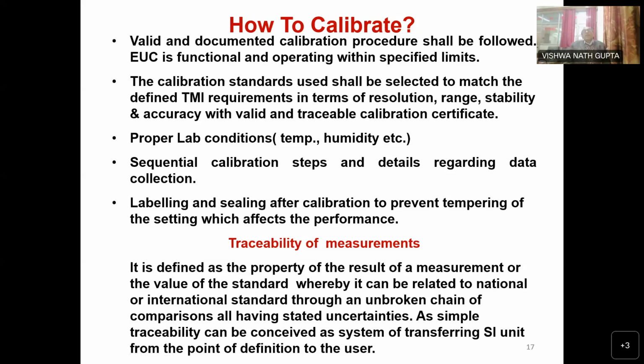Now, once we emphasize the calibration of electrical equipment for industry, the same applies to us also. Our measurements should also be traceable to national standards, meaning the chain of traceability has to be maintained. Suppose from the SI to the NMI, like our NPL, whatever deviation there is, then from NPL to EITL or IDMI, that should be incorporated. And again, once we calibrate our instrument from there, the uncertainty in that calibration certificate should also be incorporated in our calibration certificate, so that the industry using it knows how much error there is, how accurate their instrument is, and how uncertain they are about their measurements.